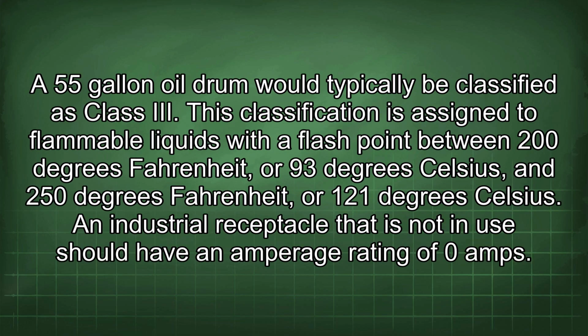A 55-gallon oil drum would typically be classified as Class Roman III. This classification is assigned to flammable liquids with a flash point between 200 degrees Fahrenheit or 93 degrees Celsius and 250 degrees Fahrenheit or 121 degrees Celsius.